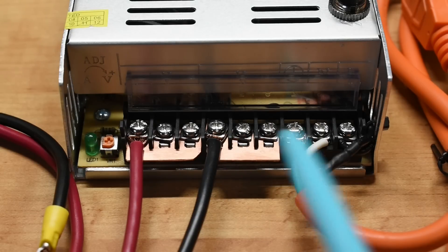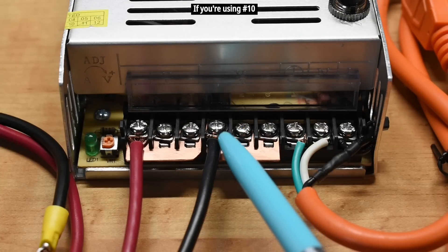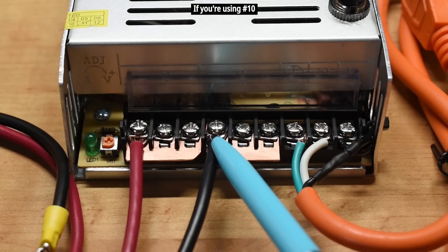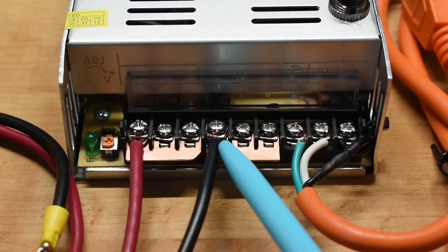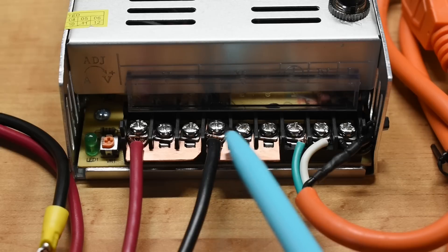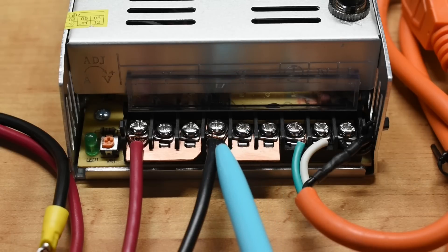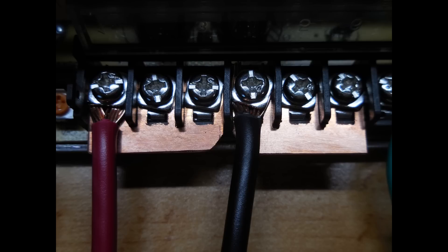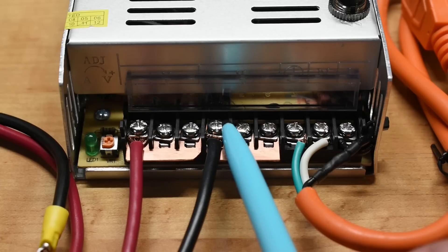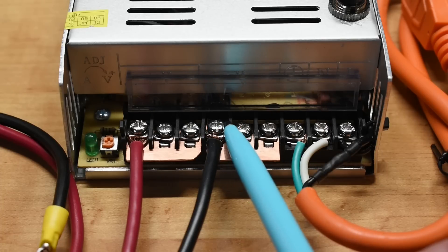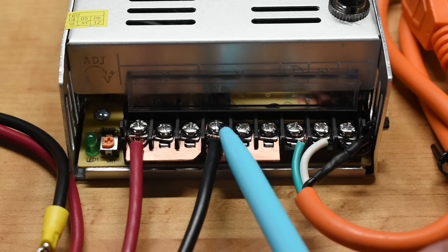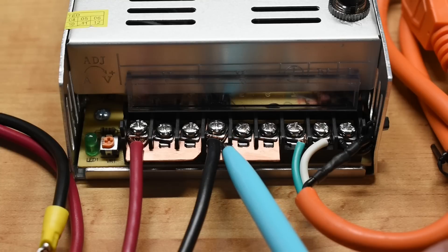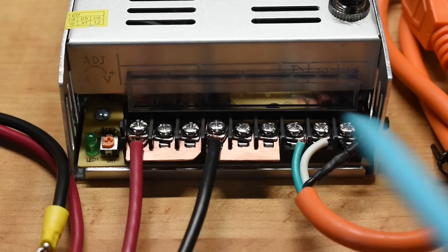When you insert the stranded copper wire, what you want to do is you don't want to bundle all the wire up and shove it to one side. You want to take that stranded wire, separate it into two groups that are equal, then you're going to push one group to one side of the screw, and the other group to the opposite side of the screw. So both bundles are underneath the head of that screw. You can push the wire all the way in. When you tighten it down, it's going to be a very level connection. The head of the screw won't be angled, and you'll have very good contact with the plate underneath if you're using one.